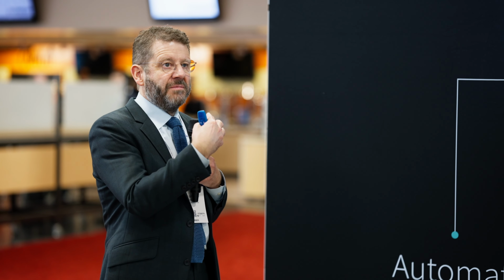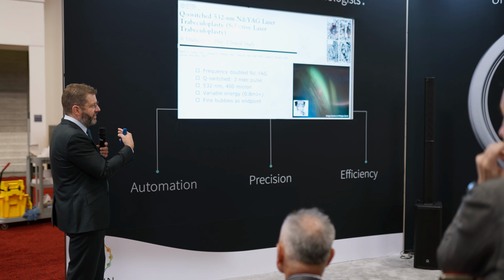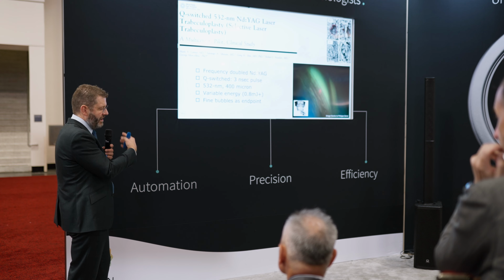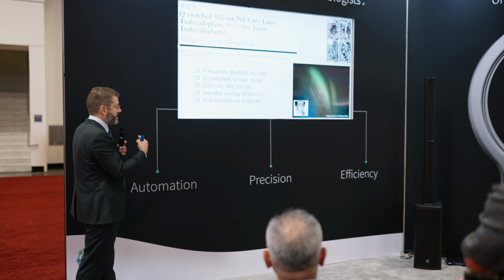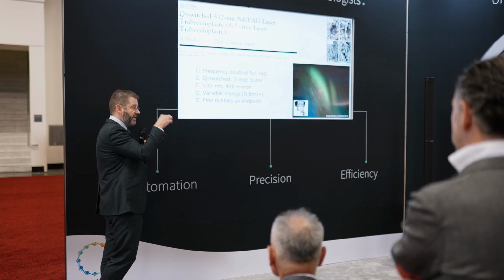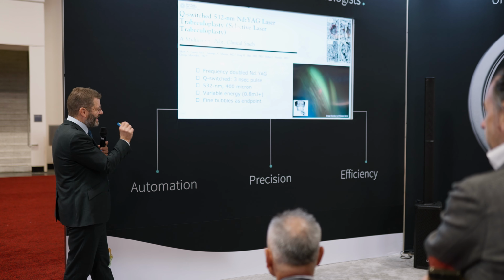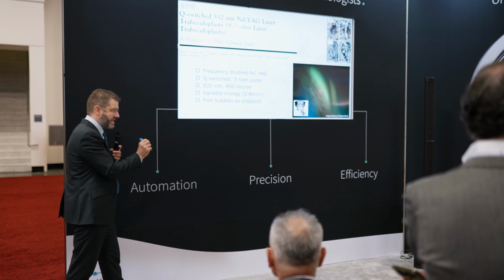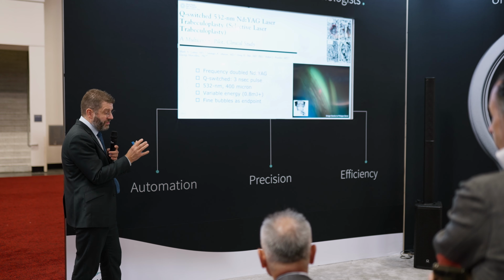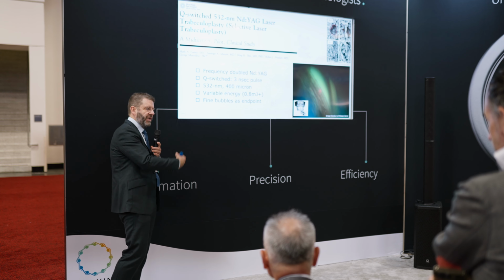And in that time, other lasers have been put on the market, other lasers have been talked about. None of the other lasers that are out there are truly selective, because the critical science that underlies the choice of parameters for any form of true SLT laser, whether it's direct SLT or whether it's gonioscopy delivered SLT, is the 3 nanosecond pulse duration, which is shorter than the thermal relaxation time of the melanin, which means that you don't get thermal spreading, so you don't get heating and cooking of the tissues.